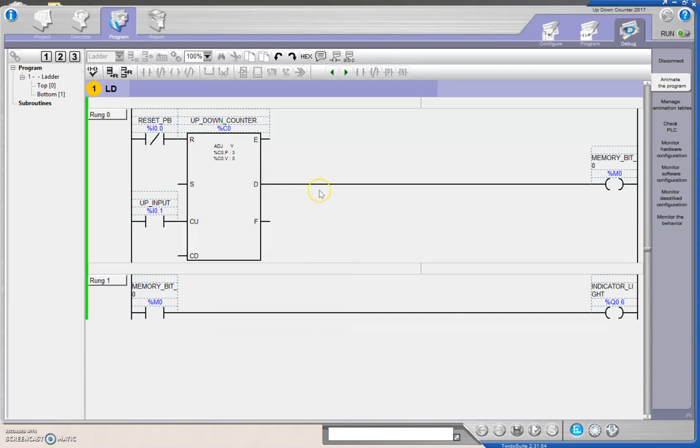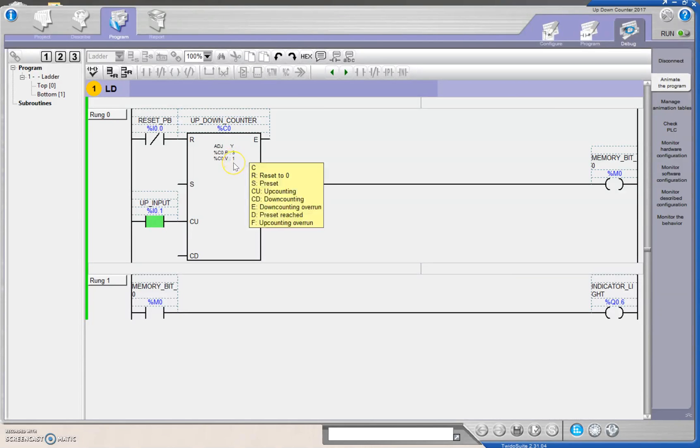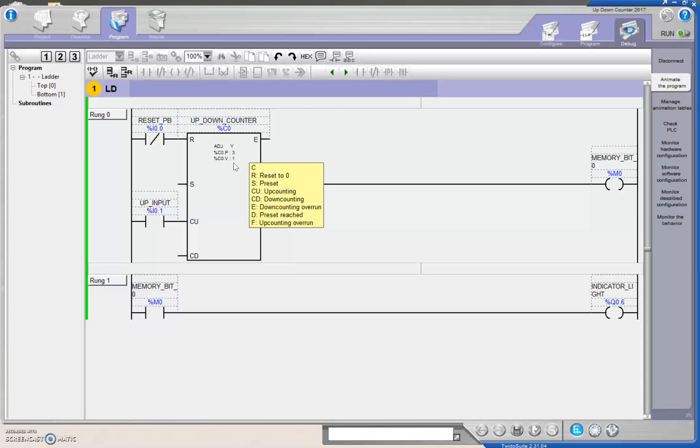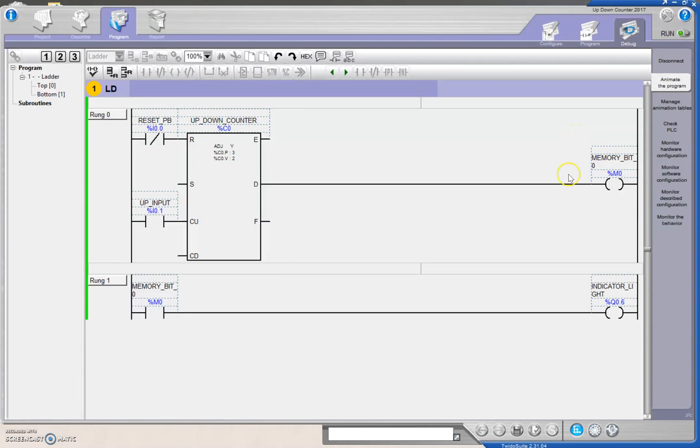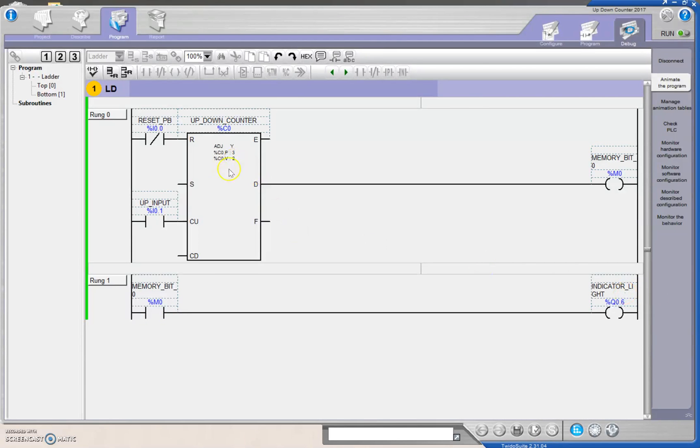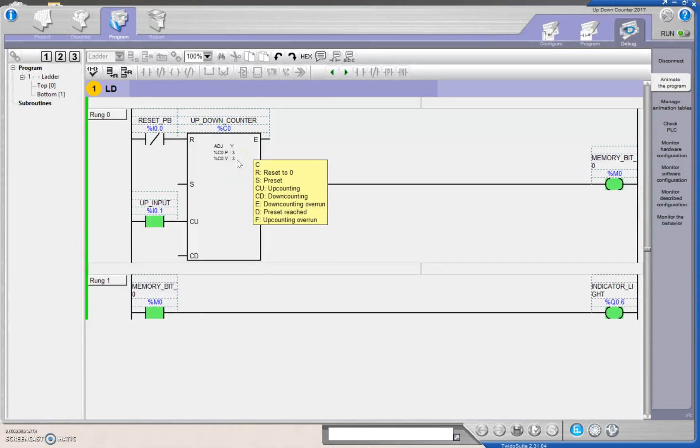So now I'm going to hit my up push button. You can see that go green. And every time that I hit that, I want you to notice the accumulated value goes up. So it went from a 0 to a 1. I let go of it. Now I have another input coming in because I'm going to press that push button. And it goes to a 2. And then, once the preset equals the accumulated value, then this memory bit will set, which will turn this to a 1. And that will set off my indicator light. So we'll hit this input one more time. And watch when these two values become the same. Beautiful. And then the indicator light turns on.